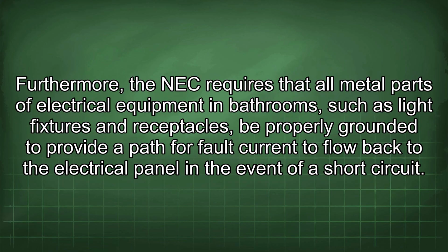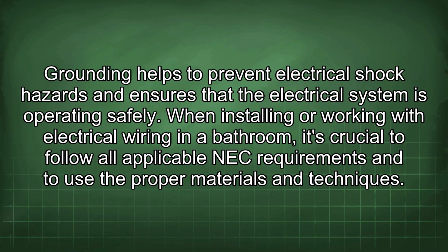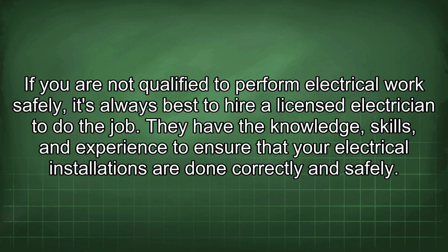Furthermore, the NEC requires that all metal parts of electrical equipment in bathrooms, such as light fixtures and receptacles, be properly grounded to provide a path for fault current to flow back to the electrical panel in the event of a short circuit. Grounding helps to prevent electrical shock hazards and ensures that the electrical system is operating safely. When installing or working with electrical wiring in a bathroom, it's crucial to follow all applicable NEC requirements and to use the proper materials and techniques. If you are not qualified to perform electrical work safely, it's always best to hire a licensed electrician to do the job. They have the knowledge, skills, and experience to ensure that your electrical installations are done correctly and safely.